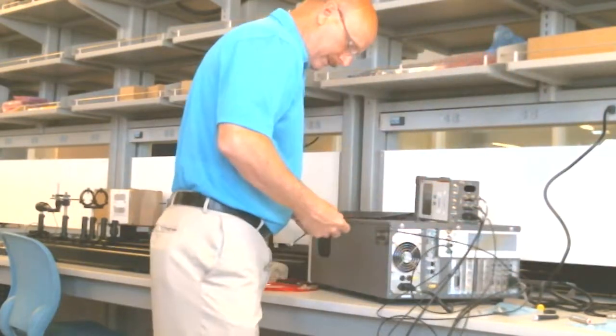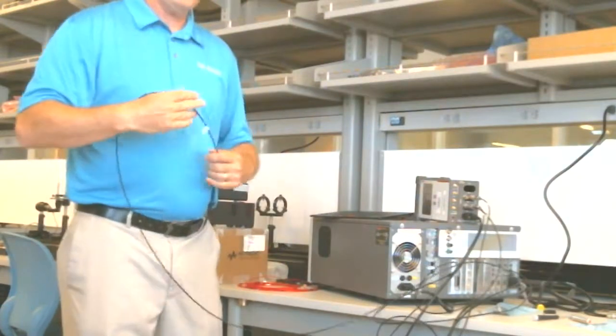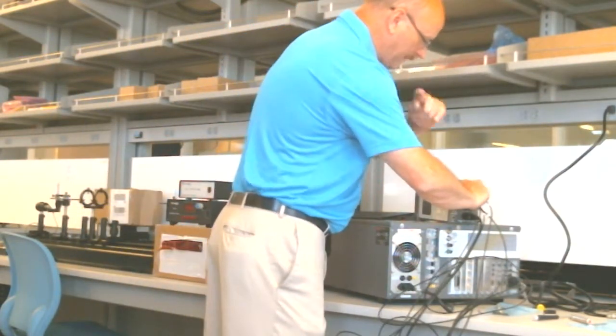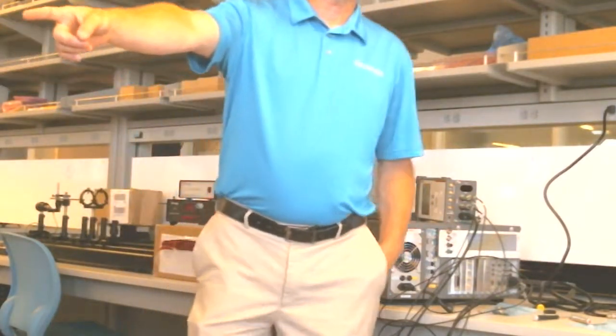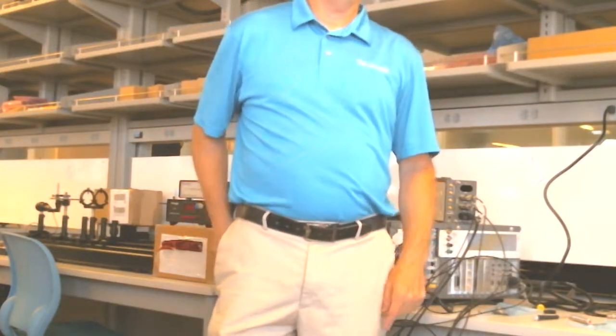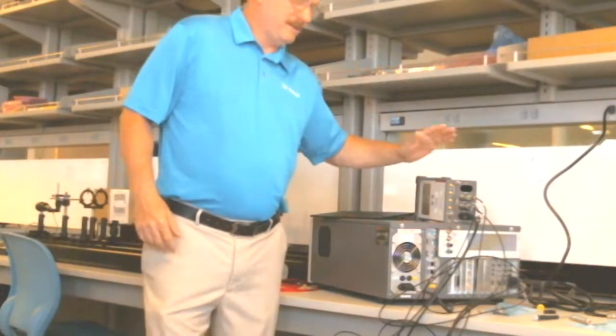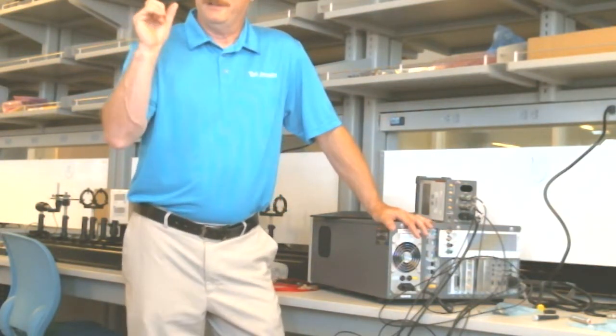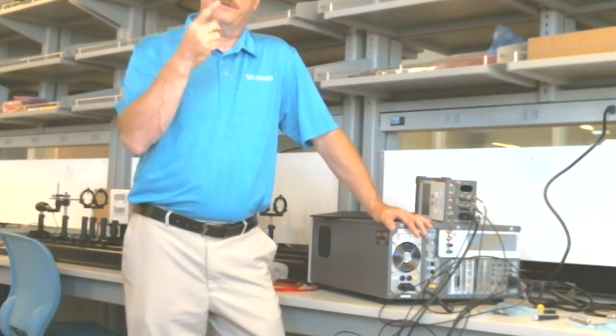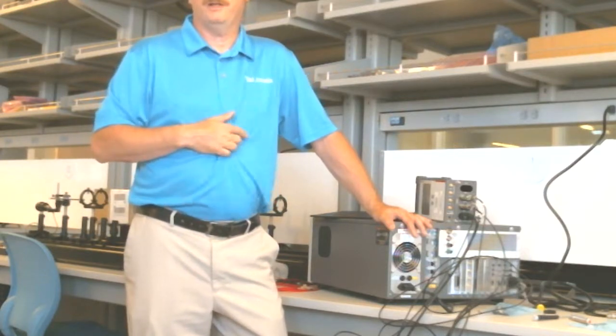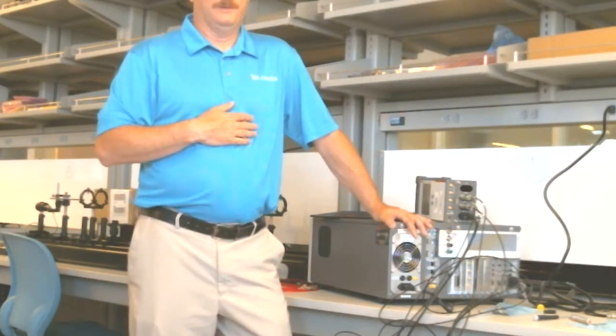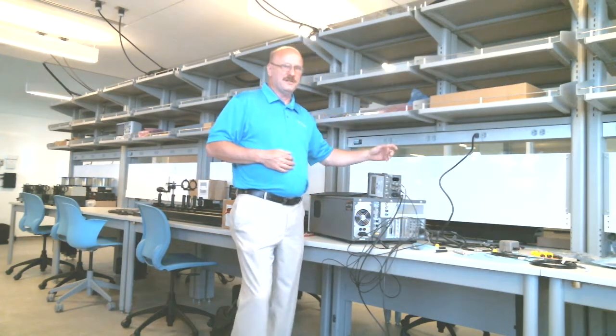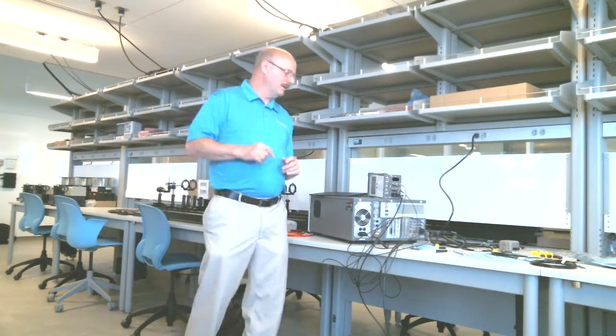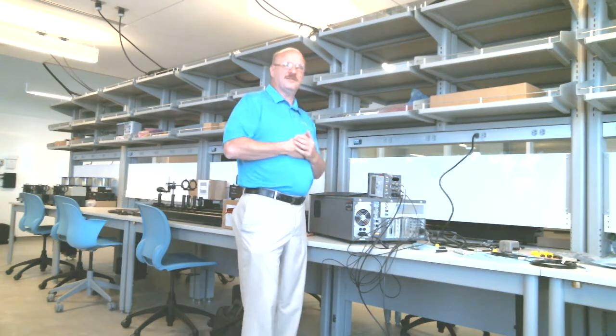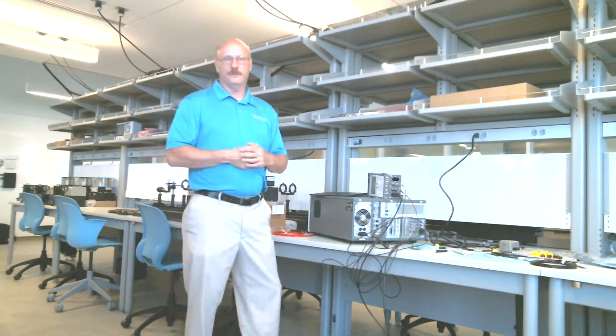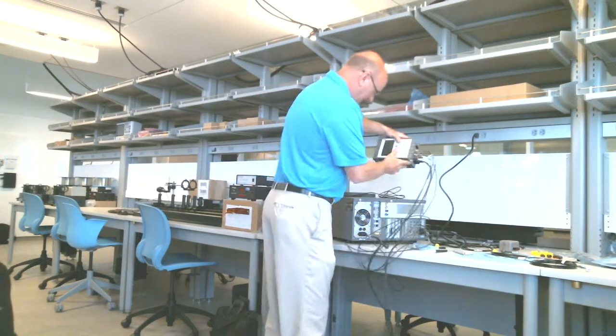Now, we talked a little bit about 2-wire and 4-wire measurements. This system will auto-detect that. That system over there won't. So if you have 4 wires coming off of there, force and sense to your device, and you don't tell it, I want to do a 4-wire measurement, you're not going to get a 4-wire measurement. This has resistance between the sense leads and the high leads, and if it senses a current flowing through there, it knows you've connected those leads, and it will automatically put it in a 4-wire mode, remote sense mode. Okay. So I don't have to use both of these cables. I can just use the force, and that's what I'm going to do for demo purposes here, and I'll show you. You don't need that kind of accuracy. But when you connect those sense leads, it automatically knows you've done that, and it improves your accuracy. Okay. So we only have channel 4, so we're not going to do anything with channel 4.